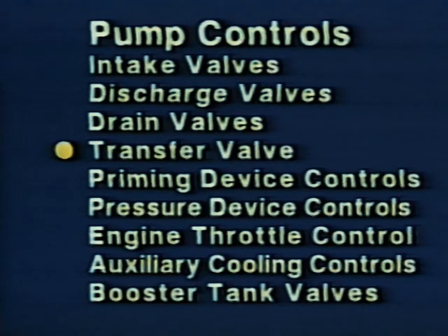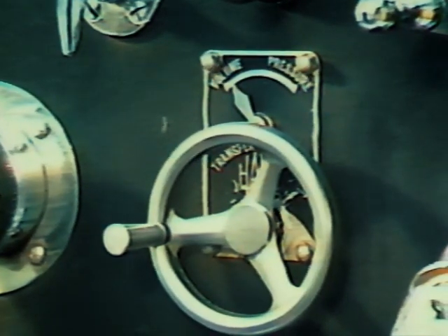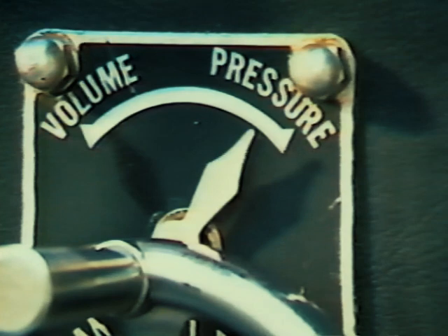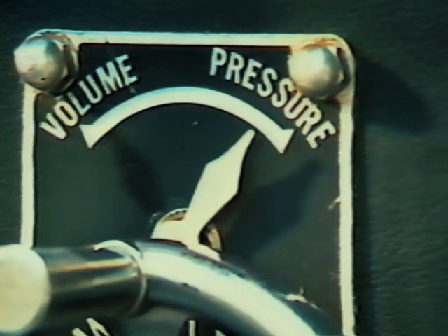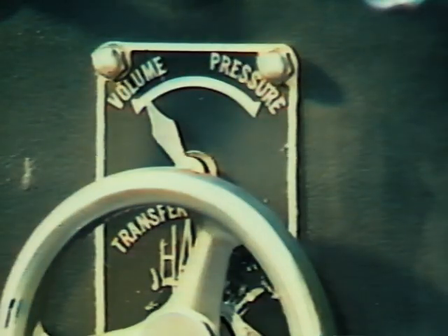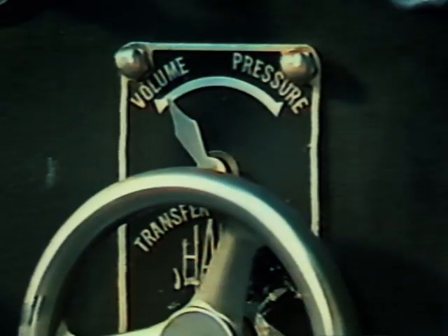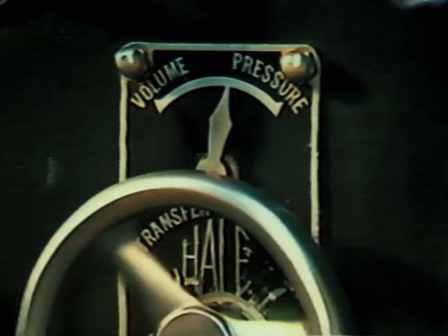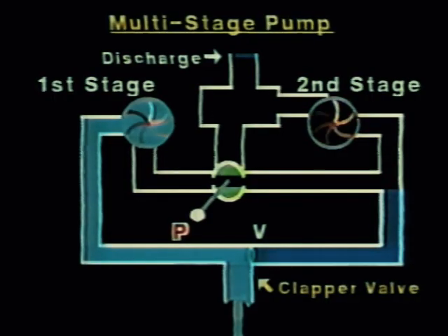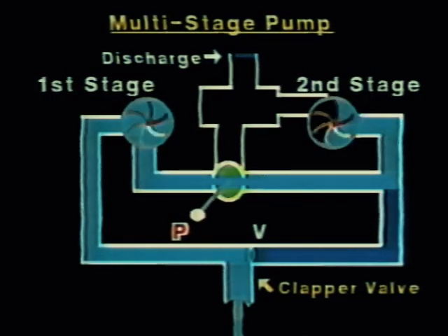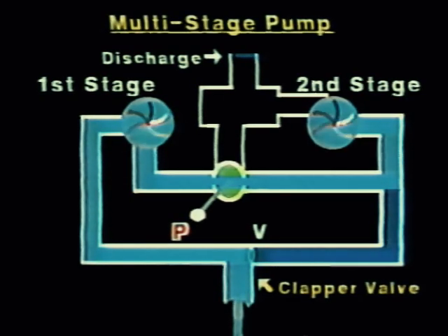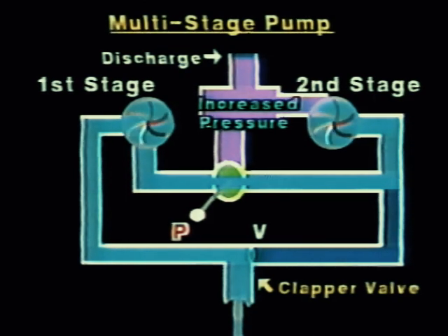A transfer valve will also be found on apparatus with the series parallel centrifugal pump. This valve is used to control the pressure or volume of water being pumped during a pumping operation. The valve has two settings, which may be designated as pressure volume or series parallel. Series designates the pressure position, and parallel the volume position. To create higher pressure, place the valve in the pressure or series position. In this position, the valve channels water directly from the discharge outlet of the first stage of the pump to the inlet eye of the second stage, where water pressure is increased, then discharged to the discharge outlet.